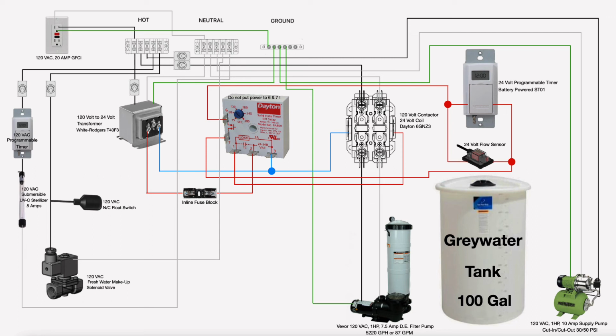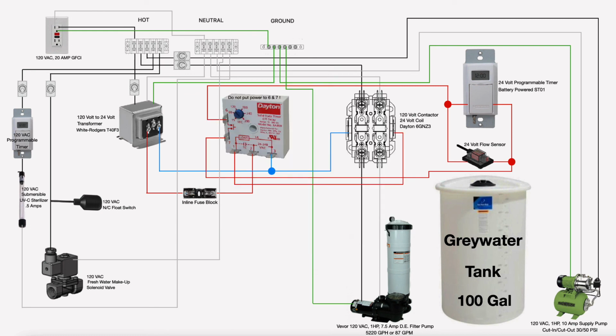So it'll allow that pump to run for 5 minutes, and then it's going to shut off. Whereas if it receives a signal from the programmable battery-powered timer, and that battery-powered timer continues to send a signal to the time delay relay for 1 or 2 hours, that relay is going to continue to send 24 volts to that contactor coil to allow that filter pump to run for that 1 or 2 hours. Once the relay stops receiving that trigger signal from that programmable battery-powered timer, then the internal time delay timer in the relay itself will begin its 5-minute countdown and just run for that next 5 minutes, and then it will open its contacts and stop sending 24 volts to the coil on the contactor, thereby shutting off the filter pump.